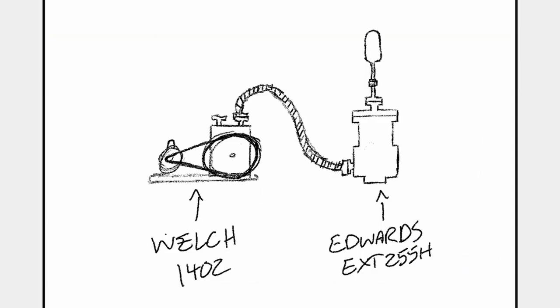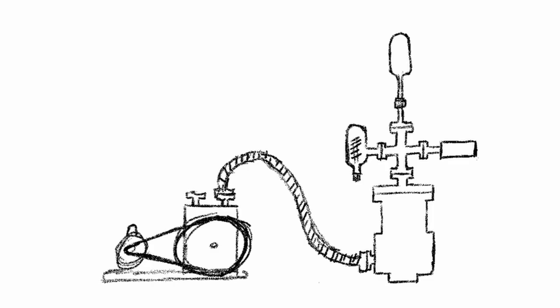Now the main problem with this system, which you may have already noticed, is that we don't actually have any way of measuring the vacuum inside the vacuum chamber. In fact, we don't even know when it's safe to turn on the turbo molecular pump because we don't have any way to read our roughing pressure, and so we're going to need a vacuum gauge. Actually, we're going to need two vacuum gauges. Here I've added a cross fitting to the inlet of the turbo molecular pump, and on one end I've added a Pirani gauge. The Pirani gauge can read pressure from atmospheric down to rough vacuum. On the other side I've added an ion gauge. The ion gauge can turn on once we've hit rough vacuum, and it'll continue to measure all the way down into high vacuum.